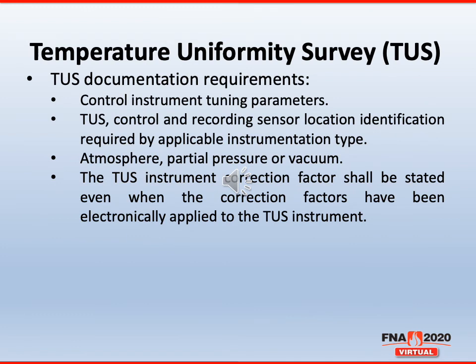When it came to TUS documentation, a few new changes are required in the documentation packages for TUSs. First off, they're going to require the control instrument tuning parameters. Also, you're going to have to provide the TUS, control and recording sensor location identification by applicable instrumentation type. For instance, if you have instrumentation type C, you're going to have to show where those recording sensors are located in a 3-dimensional space on your diagram. You have to list out the atmosphere that's being used during a uniformity survey. If you're using endo, air, partial pressure, or full vacuum, those will now be required as part of the TUS documentation. The TUS instrument correction factors shall be stated even when the correction factors have been electronically applied to the TUS instrument. So those correction factors will now have to be documented somewhere within that documentation report.